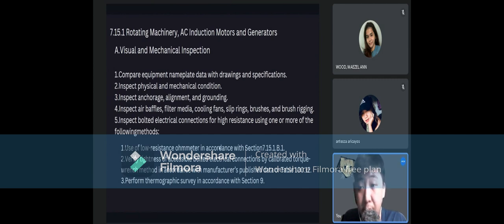3. Inspect anchorage, alignment, and grounding. Dito makikita kung may tama or kung may sira ba or defect, which is sa number 2 din, nakalagay inspect physical and mechanical condition. 4. Inspect air baffles, filter media, cooling fans, slip rings, brushes, and brush rigging. Yung mga sinabi dito is for external and internal parts na sa loob ng equipment, which if not inspected properly, can lead to the equipment breaking down, and other equipment may also break down because they are connected with one another.